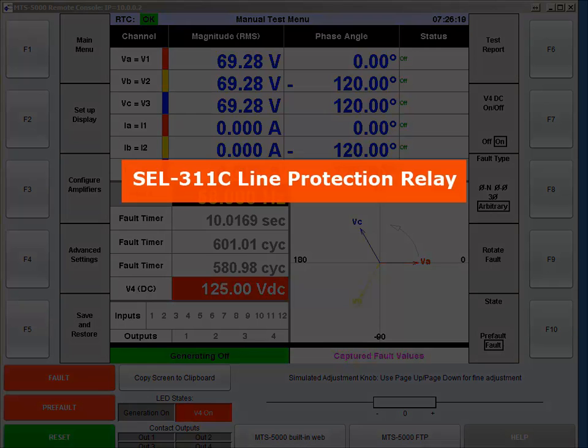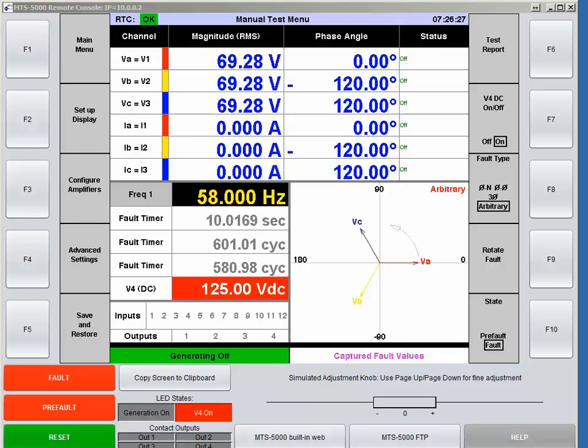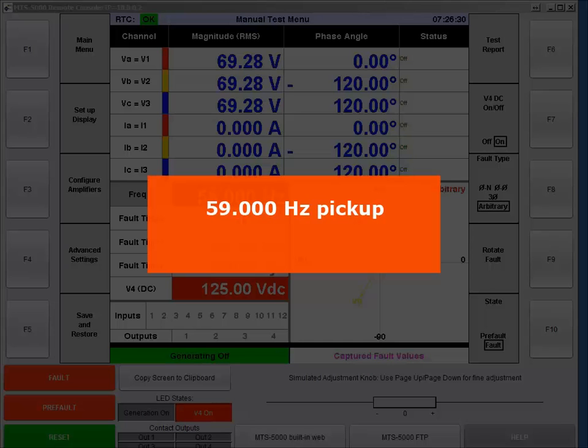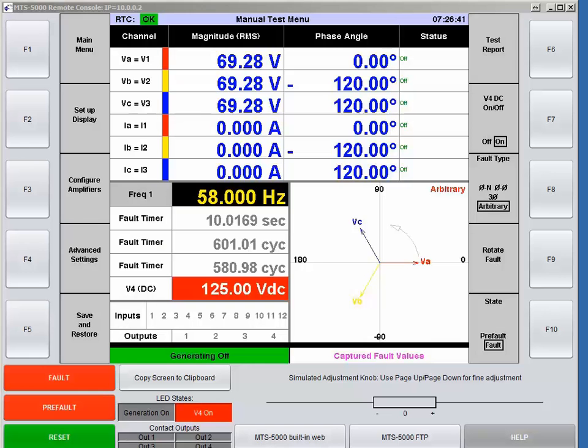One of them is an SEL 311C line protection relay and the other is a Beckwith Electric M3425A generator relay. Both relays have identical under-frequency settings with a 59 Hz pickup and a 600-cycle time delay, which means that if the frequency I inject into the relays is less than 59 Hz, those relays should operate in 600 cycles.